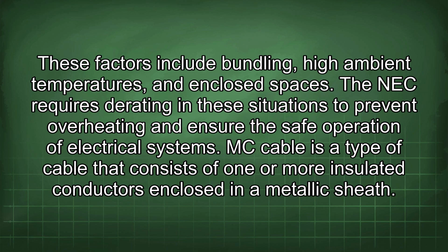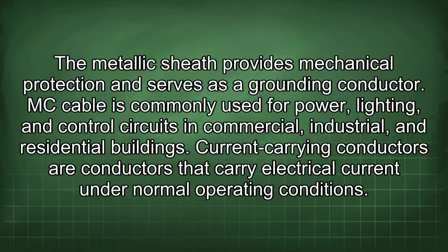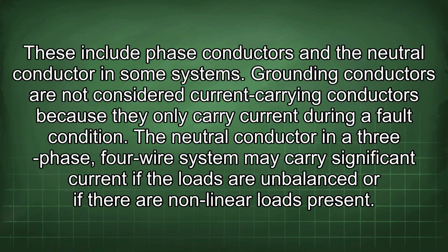MC cable is a type of cable that consists of one or more insulated conductors enclosed in a metallic sheath. The metallic sheath provides mechanical protection and serves as a grounding conductor. MC cable is commonly used for power, lighting, and control circuits in commercial, industrial, and residential buildings. Current-carrying conductors are conductors that carry electrical current under normal operating conditions. These include phase conductors and the neutral conductor in some systems. Grounding conductors are not considered current-carrying conductors because they only carry current during a fault condition.